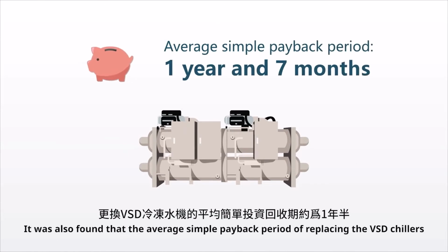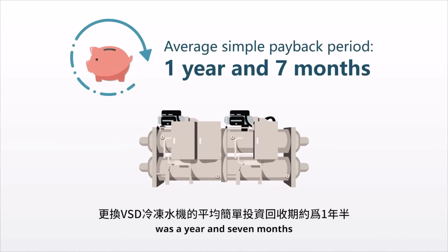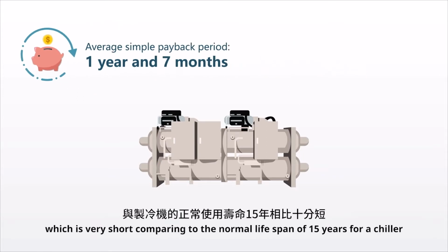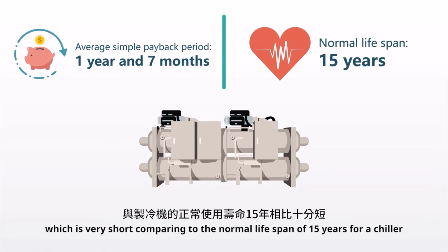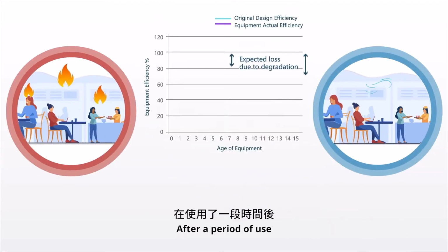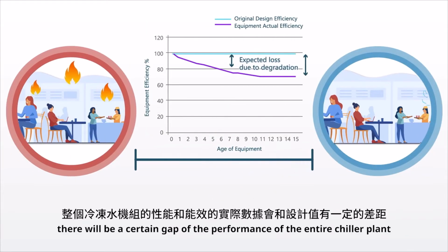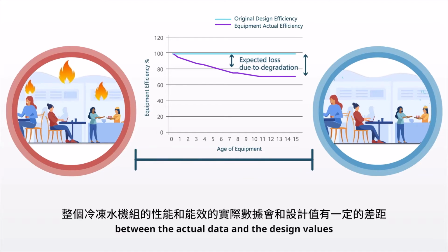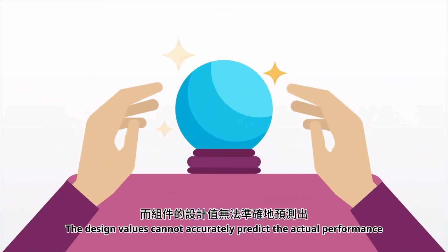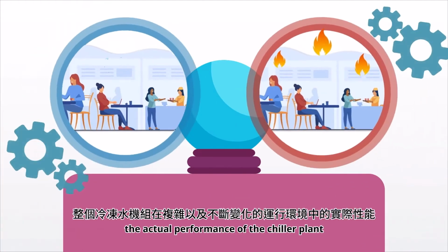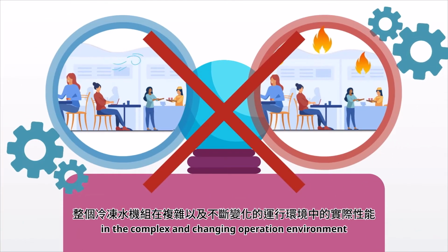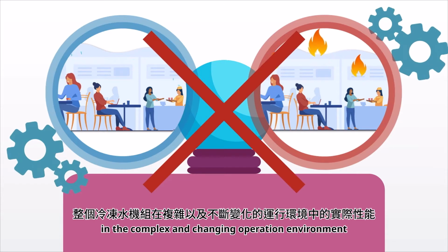It was also found that the average simple payback period of replacing with VSD chillers was a year and 7 months, which is very short compared to the normal lifespan of 15 years for a chiller. After a period of use, there will be a certain gap in the performance of the entire chiller plant between the actual data and the design values. The design values cannot accurately predict the actual performance of the chiller plant in the complex and changing operation environment.